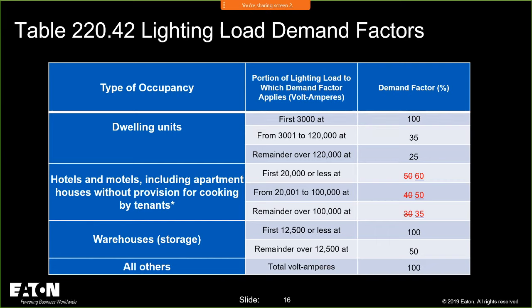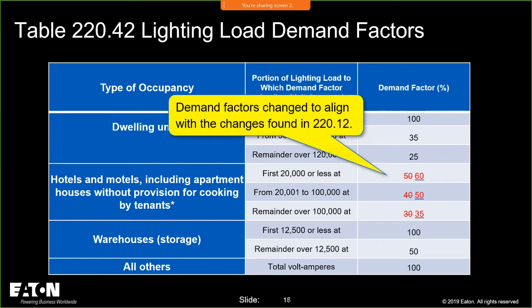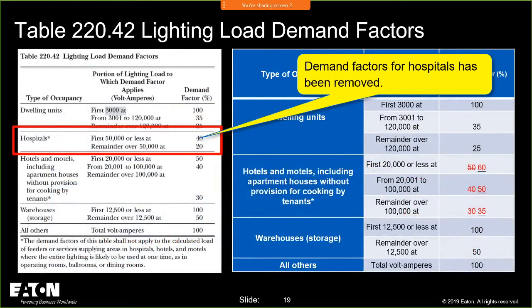Now, what you don't see in this dialogue is the hotels and motels. I'm sorry, not hotels and motels. You definitely see hotels and motels. What you don't see are the hospitals, because we removed the demand factors from the hospitals because we lowered the VA per square foot. In reality, if you think about a hospital, they're very light intensive anyway. So with regard to the lighting loads, we gave them a break on VA per square foot for the lighting loads, but we took this off, and it sort of balanced them out. I believe it's almost like a net zero for those applications. Right, wrong, or indifferent, that's sort of what we did, and it works out mathematically, from a demand and load profile perspective.